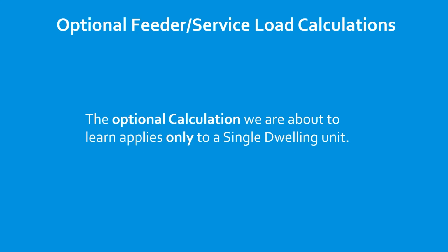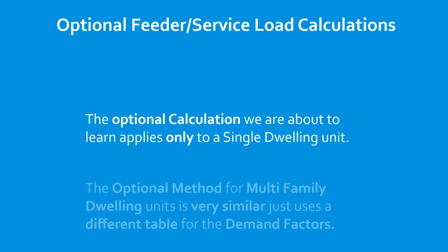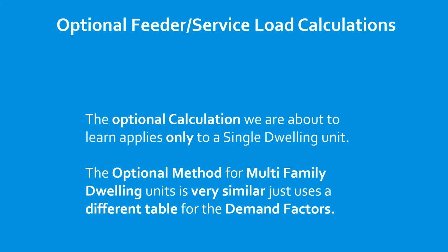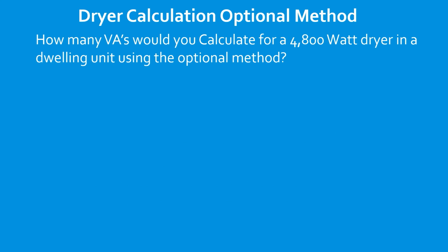The optional calculation we're about to learn applies only to single dwelling units. The optional method for multifamily dwelling units is very similar. It just uses a different table with different demand factors. Let's learn about dryer calculations using the optional method. How many VAs would you calculate for a 4,800 watt dryer in a dwelling unit using the optional method?